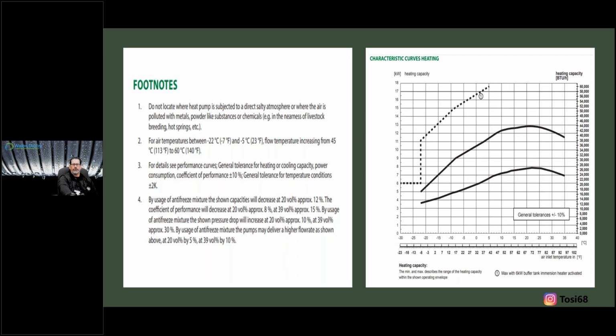The chart to the right is showing your min and your maximum. The dotted line is that 6 kW boost, because sometimes I just might need more. So that's what those charts are graphed to show you, with outdoor temperatures and delivery of BTUs. What can we achieve with the minimum and the high side of that heat pump? Do I need more? Yeah, but only in the extremes for a short window of time, because I did the math. I did envelope over the equipment again.